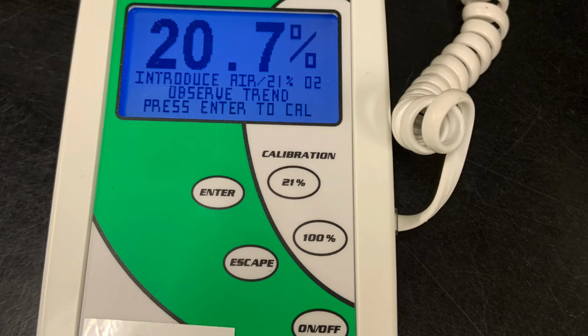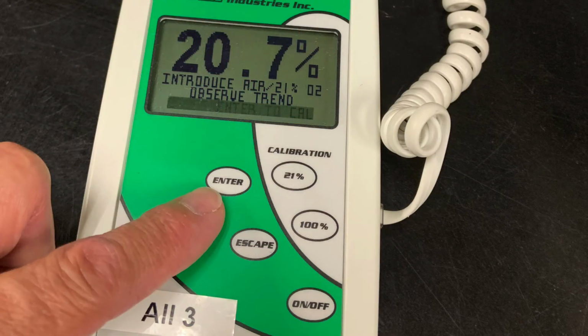To start with, we need to press the 21% calibration button, and then when we are sure that we have the probe in an environment that has 21% oxygen, we can then press the enter button on the front of this device. Once you've pressed it, whatever oxygen that probe is exposed to will now be 21% measured on the device. So you must make sure you have the probe in the right environment.